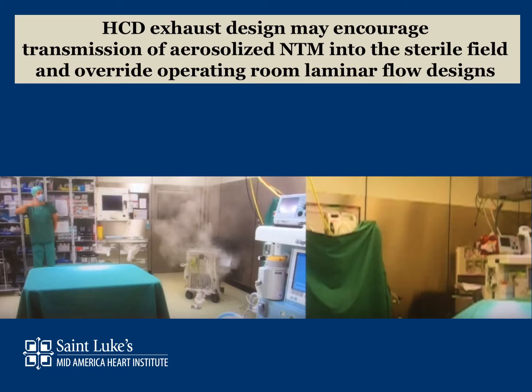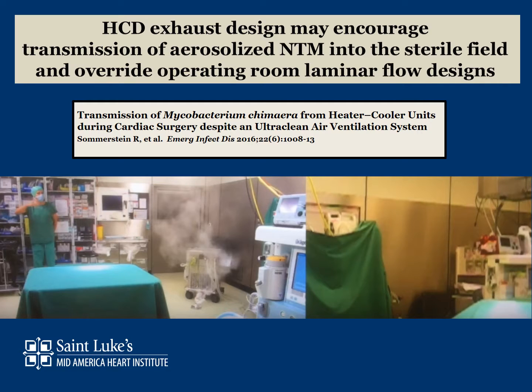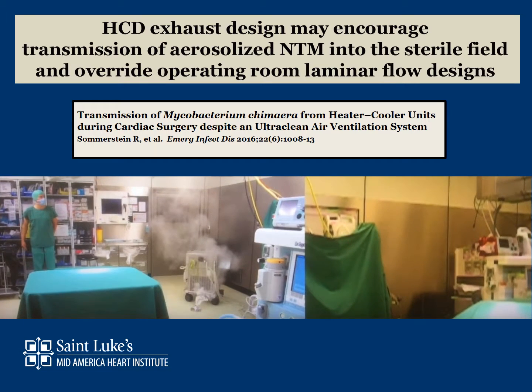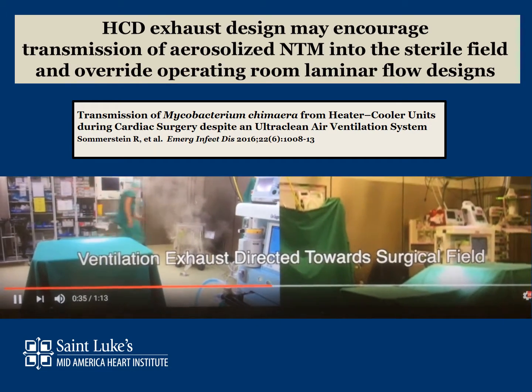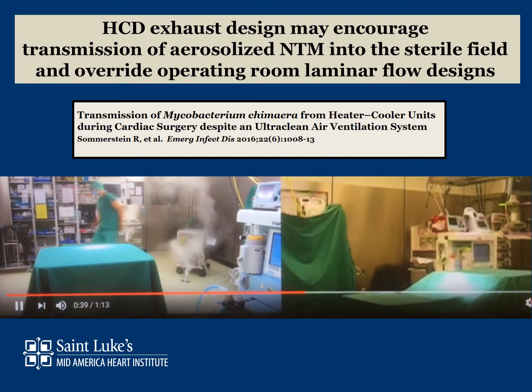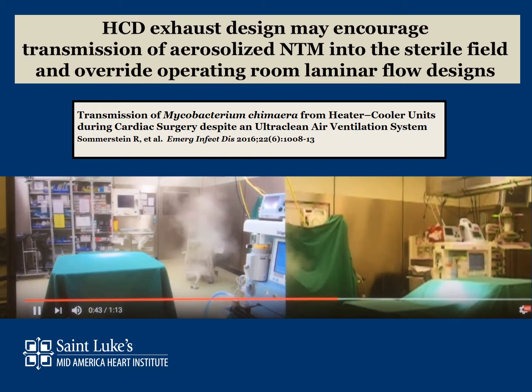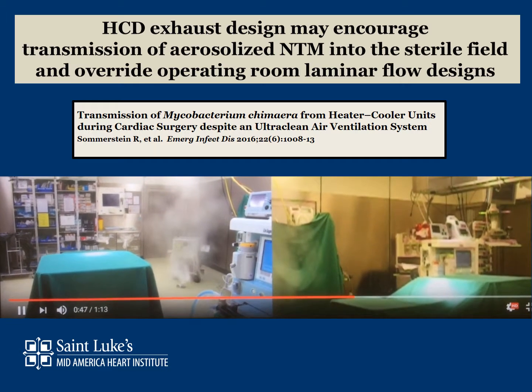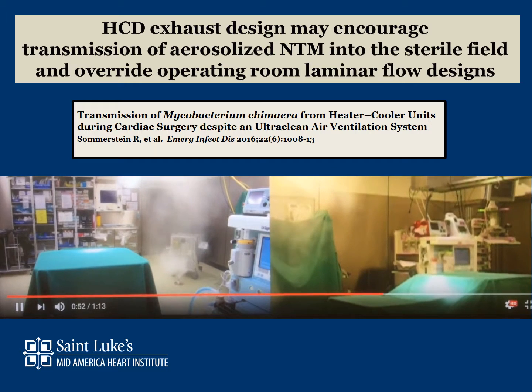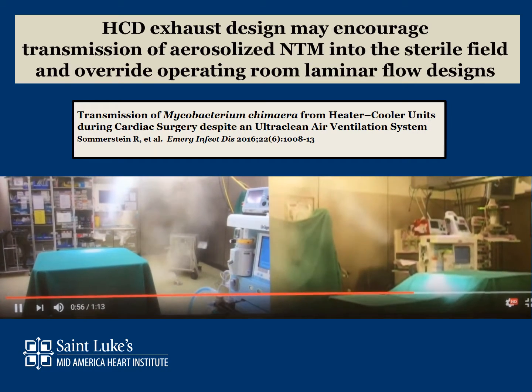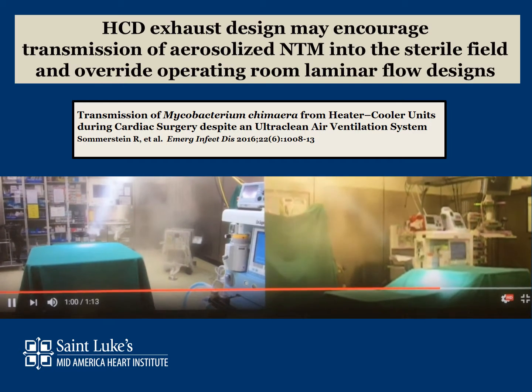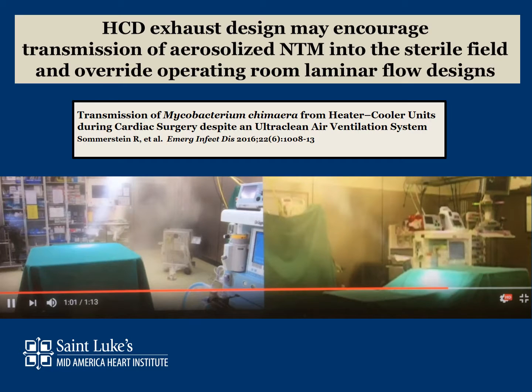The heater-cooler device design can encourage transmission of aerosolized NTM into the sterile field and override operating room laminar flow designs. Laminar flow designs are not necessarily protective. This was clearly outlined in a very nice paper by Sommerstein, and you'll see in the video, you've got a heater-cooler device with the exhaust facing the surgical field. This is a functioning operating room. Laminar flow is going. And within 10 to 12 seconds, you begin to see in the right field the smoke that represents potentially aerosolized NTM wafting and swirling over the operating room table, clearly not impacted by the laminar flow. The exhaust fans and internal fans in these devices, while they vary in strength, have a clear impact on negating the benefit of laminar flow designs.